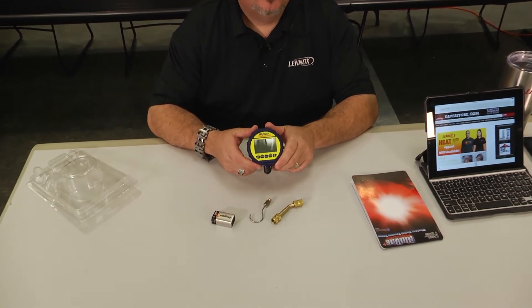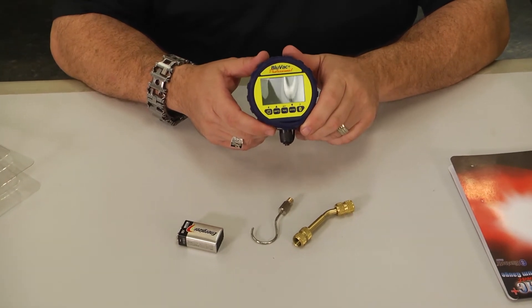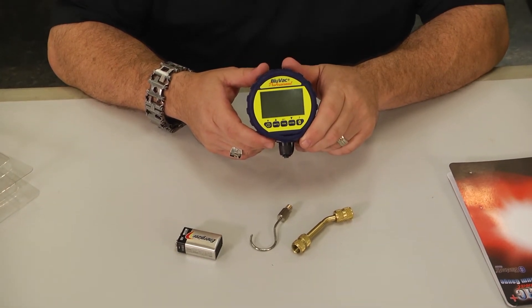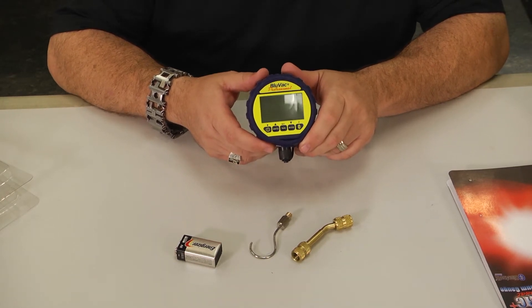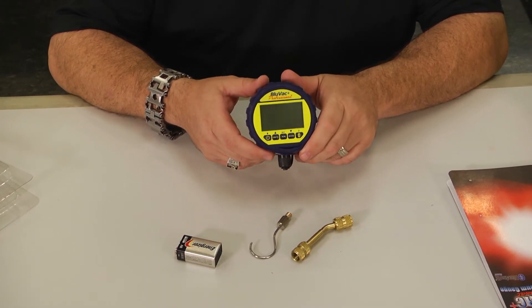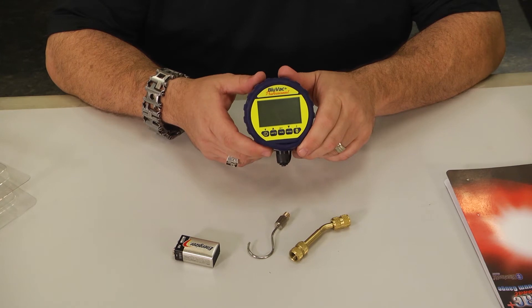Pulling a vacuum once isn't good enough — it's got to be able to stay at that vacuum level. With the technology built into the BluVac Micron Gauge and the app, whether you're using the BluVac standalone app or the MeasureQuick app, you've got the resources to know if you pulled your vacuum right, if the system still has excess moisture in it, or if it's got a leak.